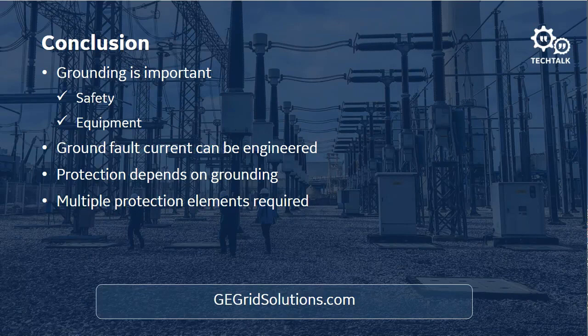The 67N is to fault locate only in the faulted generator, as well as the 87N, the ground differential, is to fault locate only on that low impedance grounded generator where the fault is. So it gives you the ability to segregate where that fault is and only trip the equipment that's faulted. And then we have typically the backup 51N, which protects you for system faults that might cause damage to your generator, but you might coordinate with those fault currents because you want the system protection to trip first. But if it fails to trip, then you want to trip your generator. Also, it's a backup protection if your 67N or your 87N fails to trip.